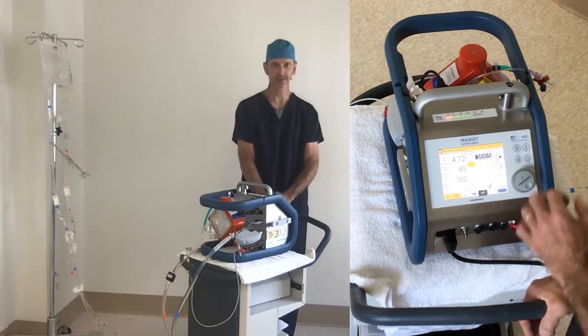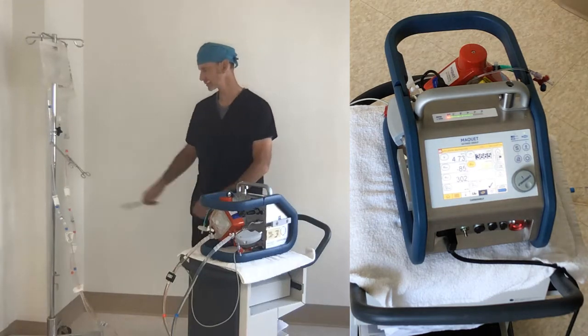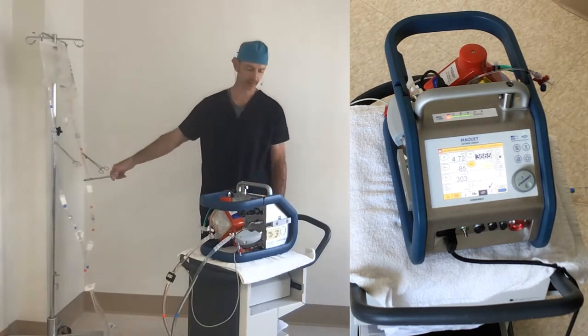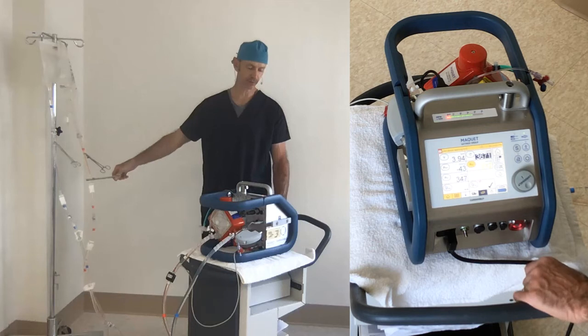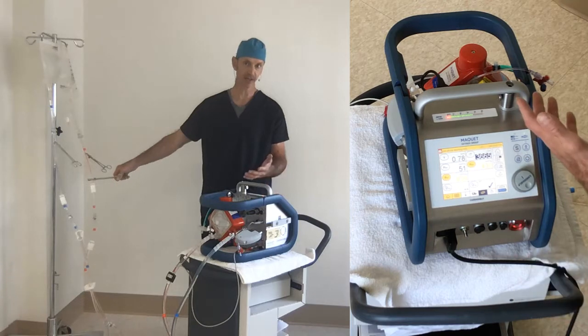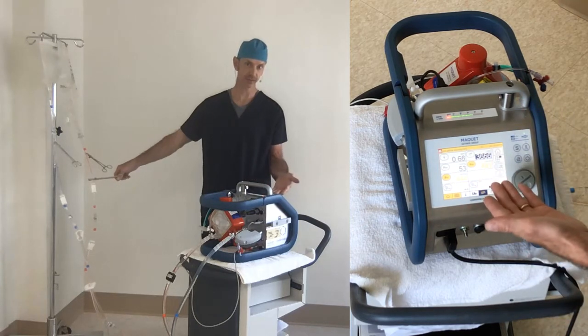We're at 287. We're getting a P-art above the warning limit. I set that to 0, so we're greater than 0, so we have a yellow alarm. And if we take a clamp and start occluding this line, then we're going to get over 327. When it gets to 327, ooh, nothing's happening. Why is nothing happening? You just saw me set it to 327.